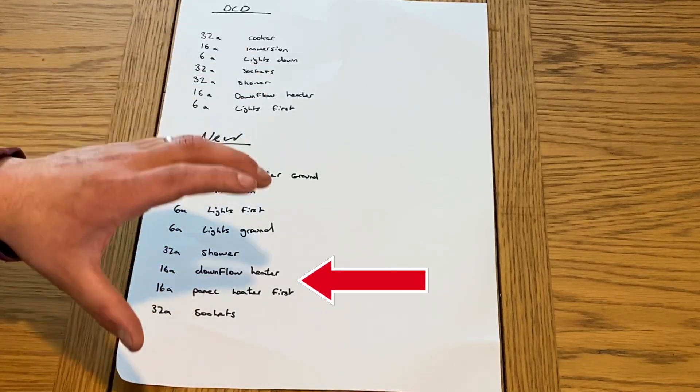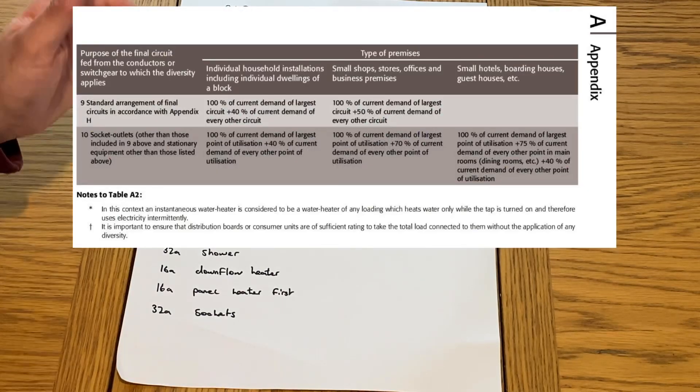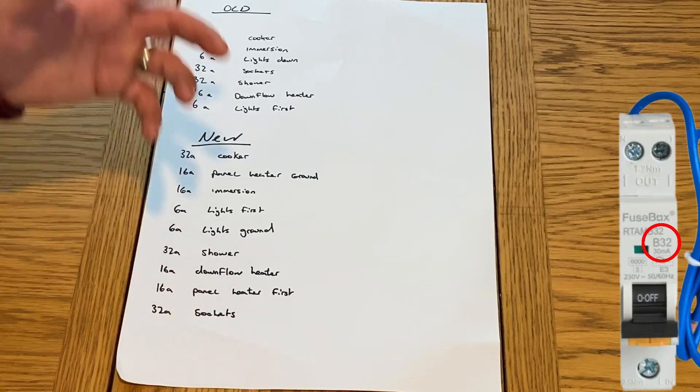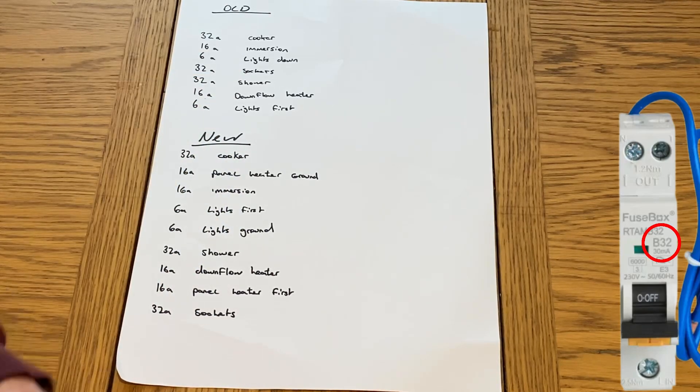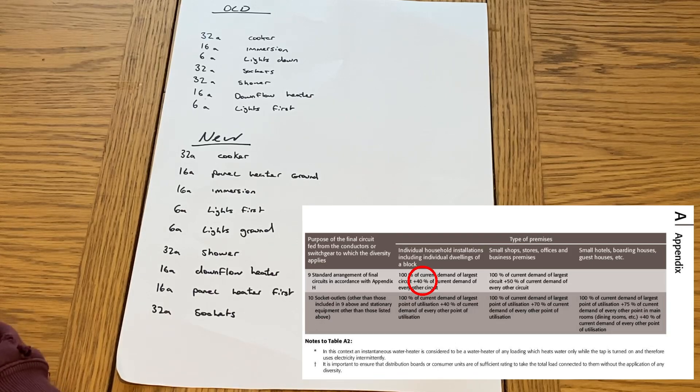The method from the on-site guide basically we're going to take 100% of the largest circuit we have. In this installation is a 32 amp, there's multiple of them so we'll just take one of them. And then what we'll do is we'll do 40% of the remainder.